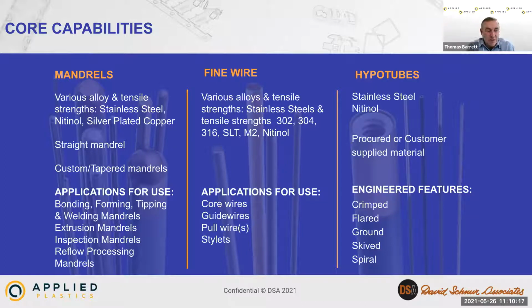Sure, thanks, Barry. Obviously the design and manufacturing engineer really must assess what's important in their process. What are the typical attributes they're going to need to develop a successful catheter and manufacturing process? So we typically get challenged around features such as durability. How durable is the coating and the mandrel going to be as part of their manufacturing process? What's the lubricious feature and how much PTFE is in that mandrel? How smooth is that going to be? And obviously that leads right into those specific release characteristics. Whether it's static or dynamic release, is it going to be sufficient for the type of process they have involved? Heat resistance: depending on the process, you're going to see various heat impact on that process and on that mandrel. So it's very important to understand what the temperature variations are, what you are going to see, and how that coating will stand up to the process.